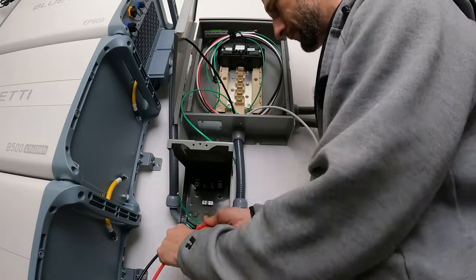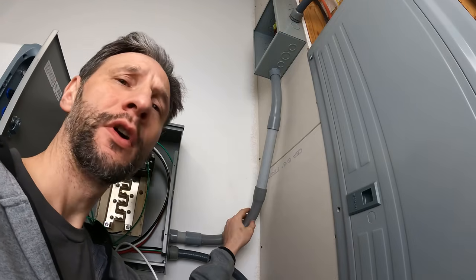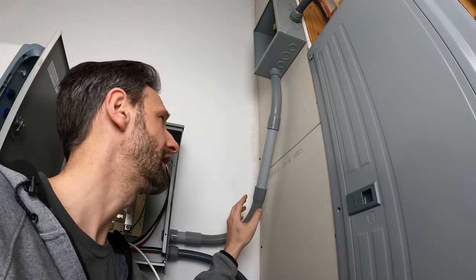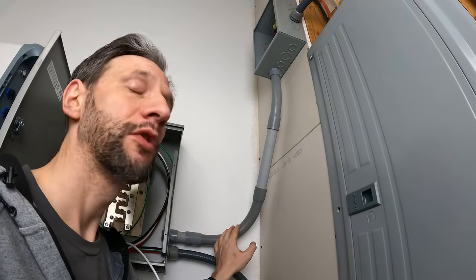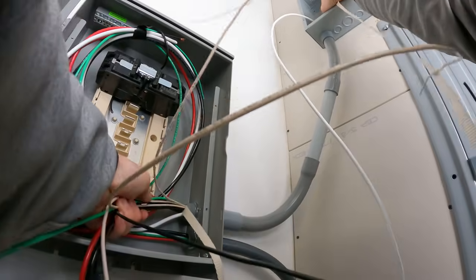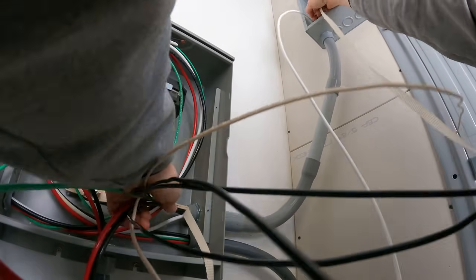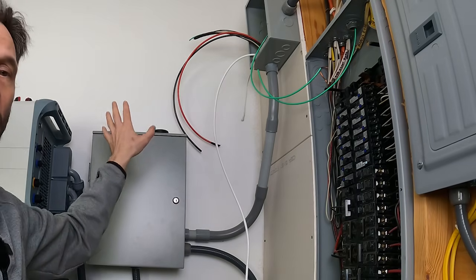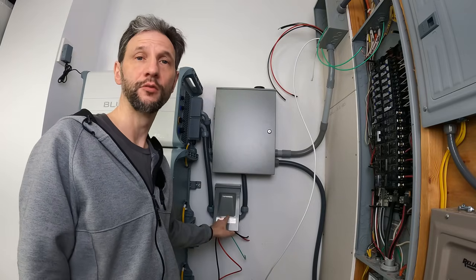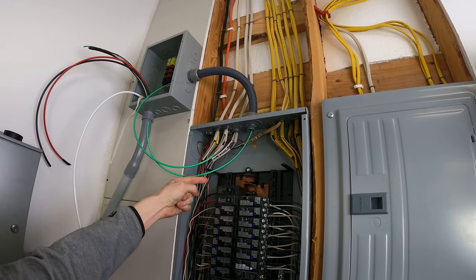I tried to pull all the wires at once, but with the 90 degree bend, it was a lot easier just to do one at a time. I realized I was going to have to put a lot more wires through this conduit than I originally planned, and when I checked the conduit fill calculator, the three quarter was not going to be enough, so I swapped it out with one inch conduit so that I can run my six gauge and the 12 gauge wires through the same conduit. The AC input power for the Bluetti is a continuous run from the 50 amp breaker through the junction box, through the sub panel, all the way to the disconnect with no breaks.